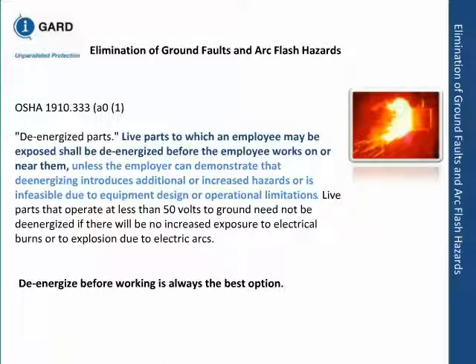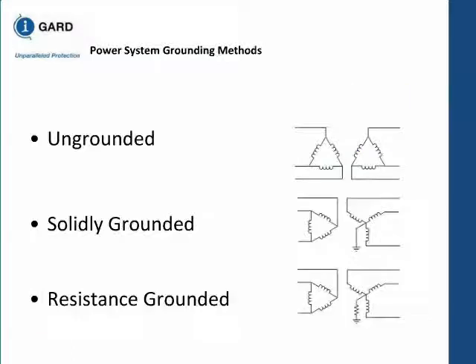Now let's shift to system grounding. That's going to be the focus. There are three grounding methods for a system. This is different than equipment grounding. You can have an ungrounded system, which was pretty normal in the process industry until the 60s. You can have a solid grounded system, which is still very widely practiced as the low-cost option. Or you can have a resistance grounded system. We'll go one by one, just the highlights of each system. Ungrounded system, normally, you don't have to do anything.